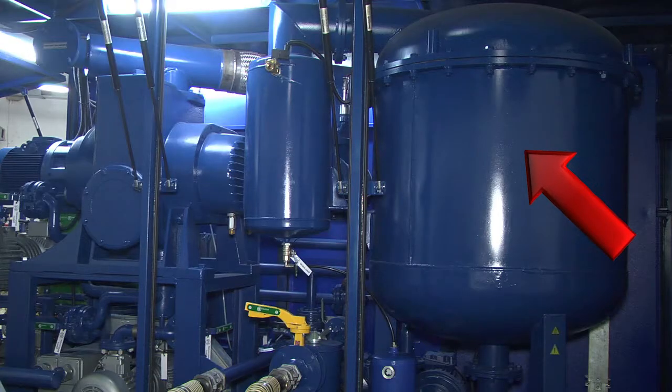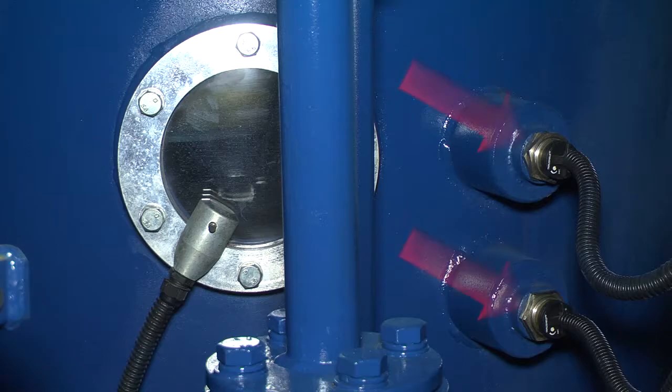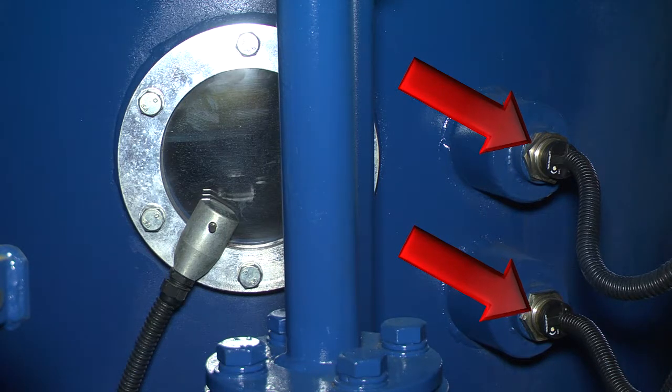The unit features vacuum column. The vacuum column assembly provides for fine atomization of the oil and has the following features: a highly efficient activator filter, high surface area of oil treatment, stable oil treatment parameters, removal of moisture to 2 ppm, reduction of gas content to 0.1%. Vacuum control automation and control system allows for automatic control of oil level in the vacuum column, control and monitoring of vacuum pumps, protection of vacuum column from oil overflow.